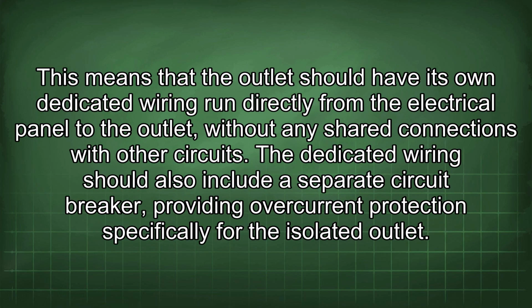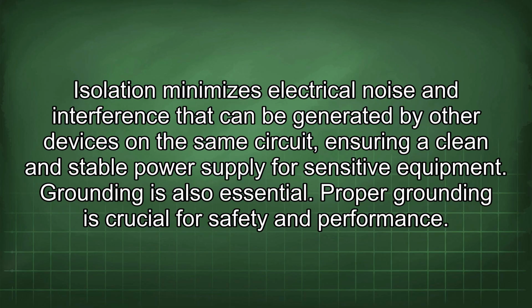This means that the outlet should have its own dedicated wiring run directly from the electrical panel to the outlet, without any shared connections with other circuits. The dedicated wiring should also include a separate circuit breaker, providing overcurrent protection specifically for the isolated outlet. Isolation minimizes electrical noise and interference that can be generated by other devices in the same circuit, ensuring a clean and stable power supply for sensitive equipment.